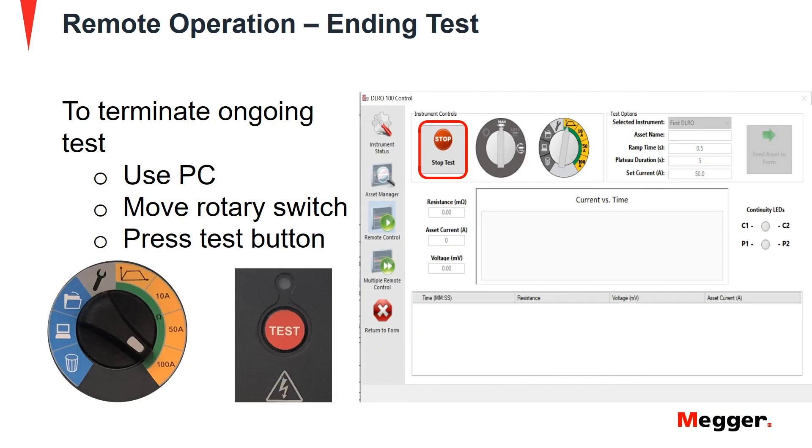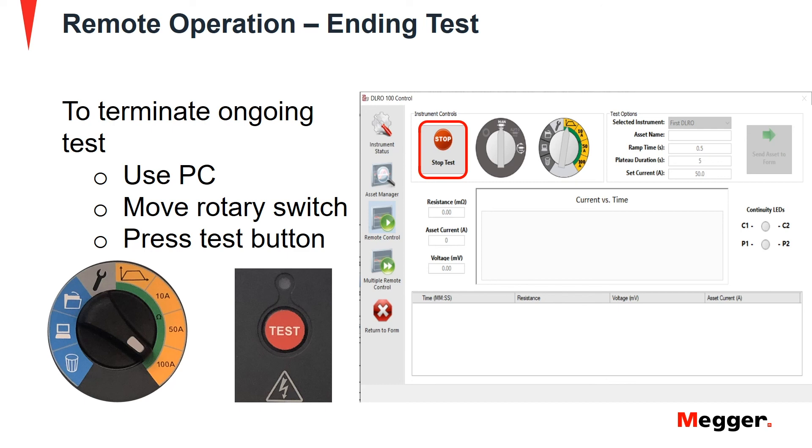To terminate an ongoing test, you can use your PC by pressing on the stop button on the DLRO100 control panel. Another way to terminate the test would be by moving the rotary switch from the laptop position to any other position or pressing the test button on the instrument.